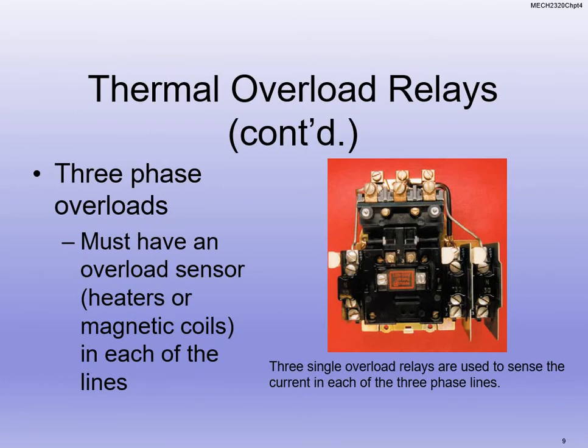So thermal overload relays, we have these on all of our motor starters. You're going to see them on all the schematics we do, everything you wire. They're built into our starters and our contactors and things like that. So it's not something separate. You can add some separate pieces, but for the most part, it's an all-in-one unit. But all three-phase motors must have overload sensors, some sort of way to protect the motor from overloading, because if you are giving it more current, it can do damage not only to the motor but to whatever equipment is in the process.